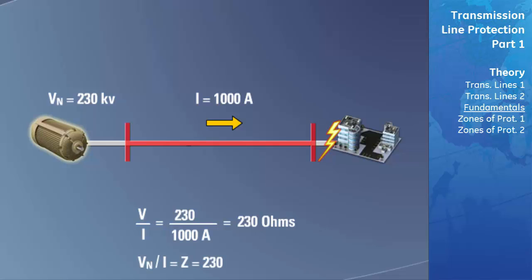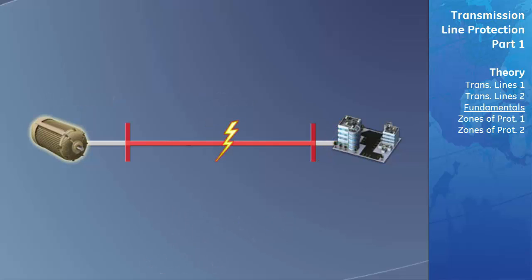The voltage will decrease because the only voltage drops now occur across the transmission line and the source impedance. In this example, the fault is located after the transmission line but before the majority of the power system load. Now the only impedance on this power system is the impedance of the source and the transmission lines before the fault. When this fault occurs, the current flowing through the transmission line will increase. The ratio of voltage over current, or impedance, will now significantly decrease. Distance relays are programmed to know the impedance to the end of the transmission line. If the impedance the relay calculates is less than the impedance of the transmission line, the relay knows that the fault is on the transmission line itself and must trip the circuit.